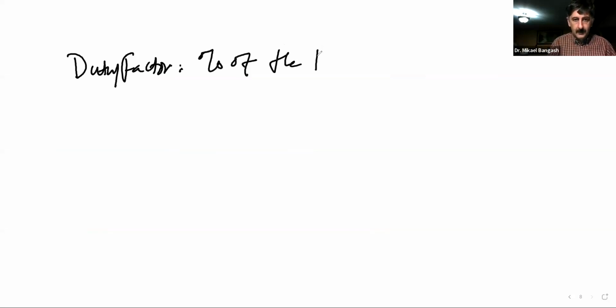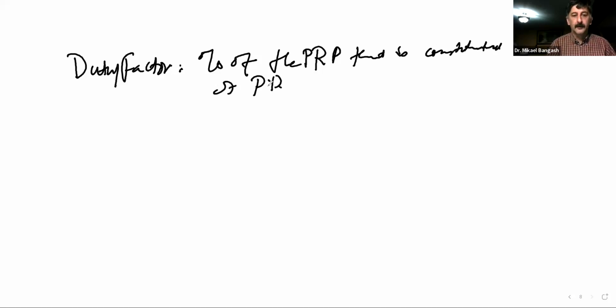Okay, so first of all, duty factor. What was duty factor? It's going to be the percentage of the PRP that is constituted of the pulse duration. Now, just keep in mind, ladies, pulse duration is also what we call on time, or talking time. So just because you don't see the words pulse duration in the definition, but you see the term on time or talking time, it will still be the same.